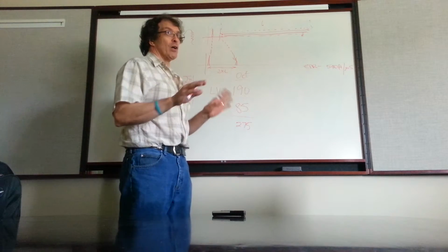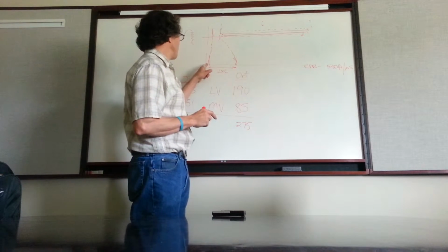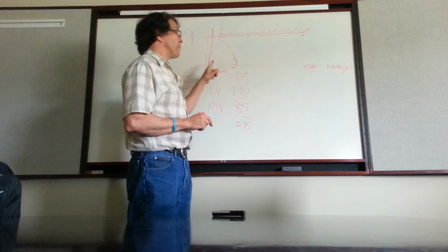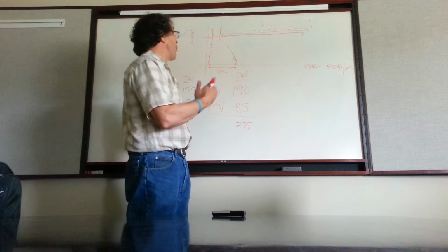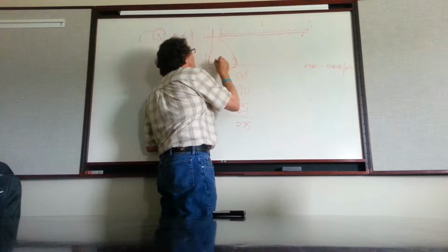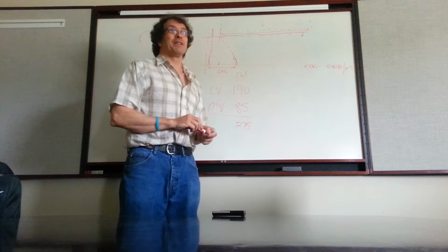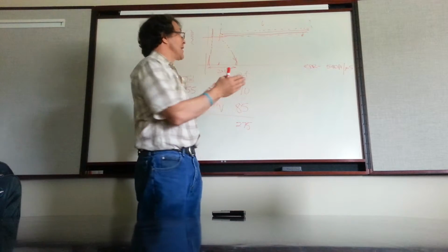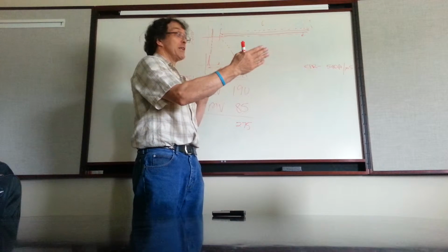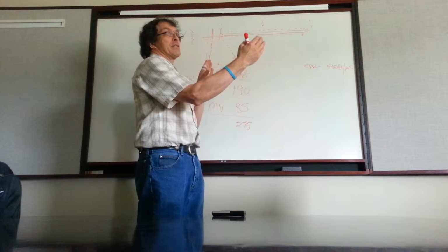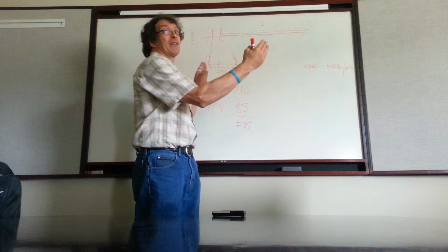Now if it was a perfect world, you'd only ever see 3 pulses. You'd see a pulse from the front, a pulse from the tail, and a pulse from the fault itself. So a front to tail. You only ever see 3, and they'd be so obvious. You'd say, "I'm good. I know where it is." That never happens. So it's useful to tell the system, or see yourself, how far they should be apart when there's no fault, because that distance gives you the length of the cable.